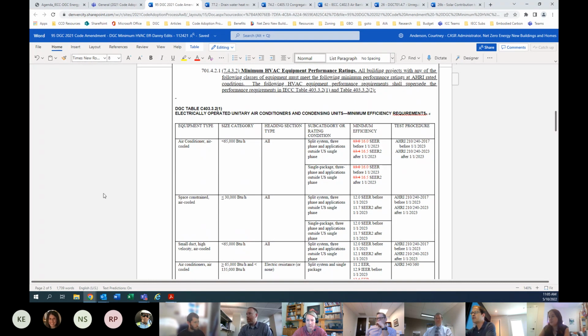So if you notice, the first row has air conditioner, air-cooled systems. There was both split system and single package. The recommendation here is to increase basically the seasonal energy efficiency ratio, or SEER, which is meant to be an aggregate or annual rating, from 13 to 16.0, or 16.5 once the new SEER 2 rating becomes available, which is January 1st, 2023. It's a similar procedure, but I think there are slightly different test conditions which would generate a different rating value. If you scroll down a little bit, Courtney, please.